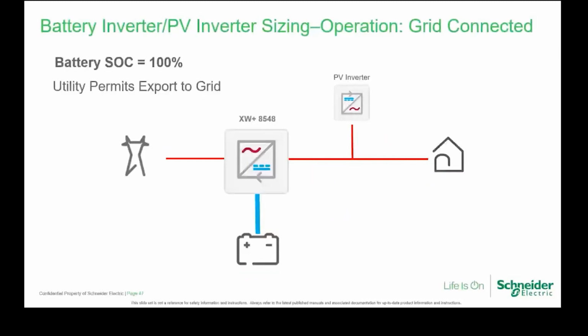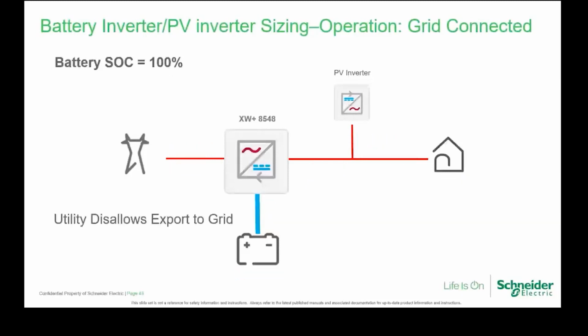At the moment, this utility allows you to export to the grid and your battery charge is 100%. So we still have a load of 1,000 watts. PV is pumping out 5,000 watts. So 4,000 watts available to go somewhere. Because your batteries are fully charged now, it's going to be zero to the battery bank and 4,000 watts to the export back to the grid. This allows export to the grid. In this case, you're not allowed to export.